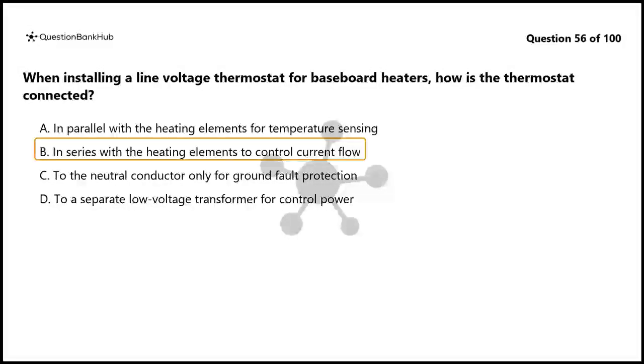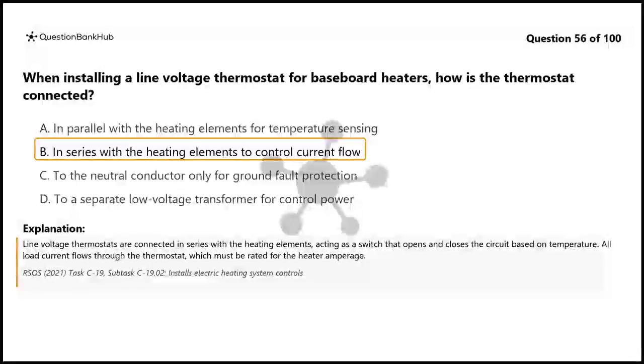The correct answer is B. In series with the heating elements to control current flow. Line voltage thermostats are connected in series with the heating elements, acting as a switch that opens and closes the circuit based on temperature. All load current flows through the thermostat, which must be rated for the heater amperage.